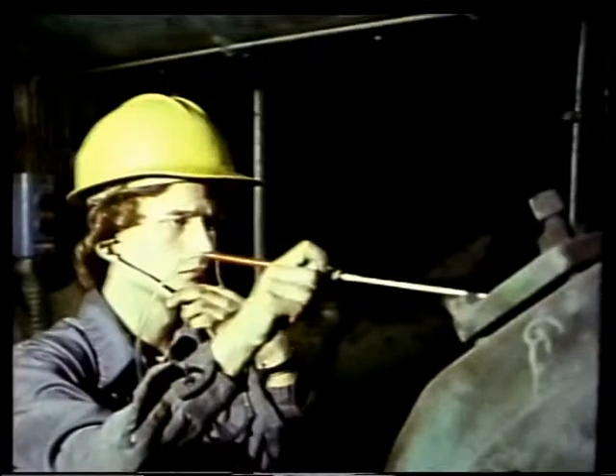The operator who checked this compressor reported a knocking noise. Now, a knock could mean anything from a bad valve to not enough lube oil. So now you have to pinpoint exactly where the knock is coming from. A stethoscope or sounding rod makes locating the noise easier.